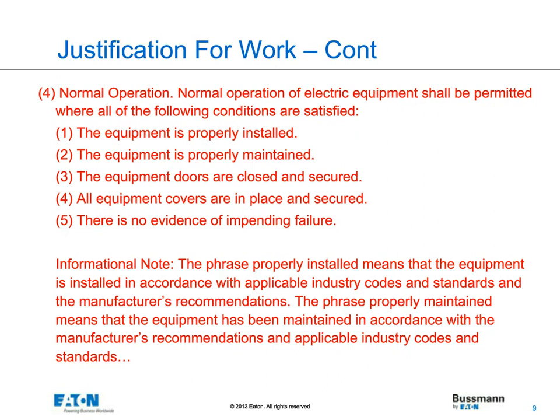And then there's an informational note there, and I captured two of the first three. It talks about what it means with regards to proper installation, i.e. installed per the NEC, or properly maintained, and that would be per the manufacturer's instructions or consensus standards, such as perhaps NFPA 70B. There's also a little bit of a note on there that's not shown on the slide here that talks about impending failure, and what would be an example of that.